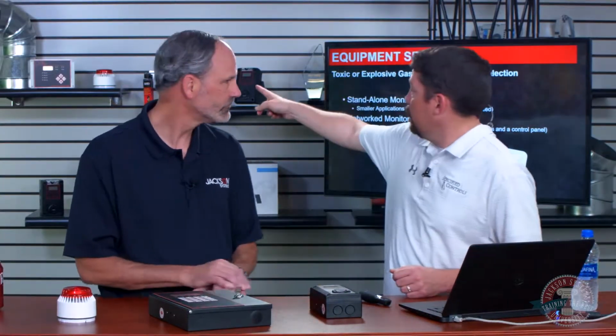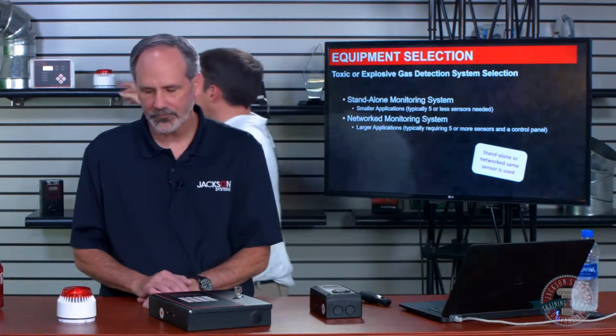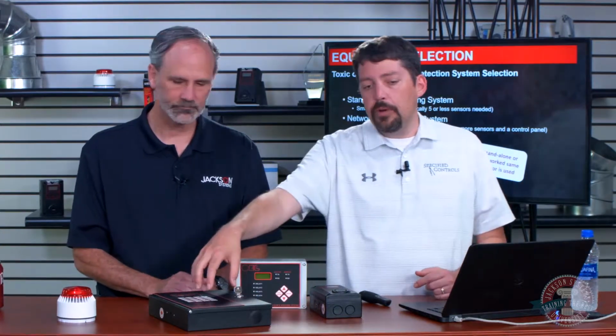It's completely standalone. We might also have a panel if there's a larger firehouse, and it's just a very small panel. Actually, this panel right up here behind us. And that is still considered a standalone situation because we're not communicating with it at all. We're not doing anything other than making sure we bring on the fan or open the damper, or whatever it might be. When we get to networked, when we talk about larger applications, we're actually communicating with our panel.